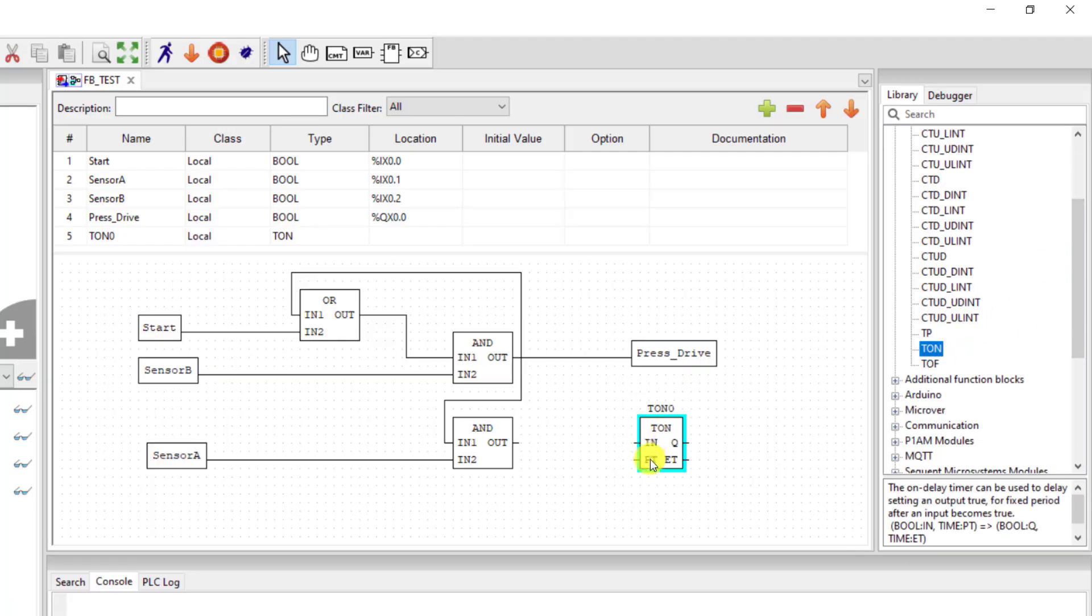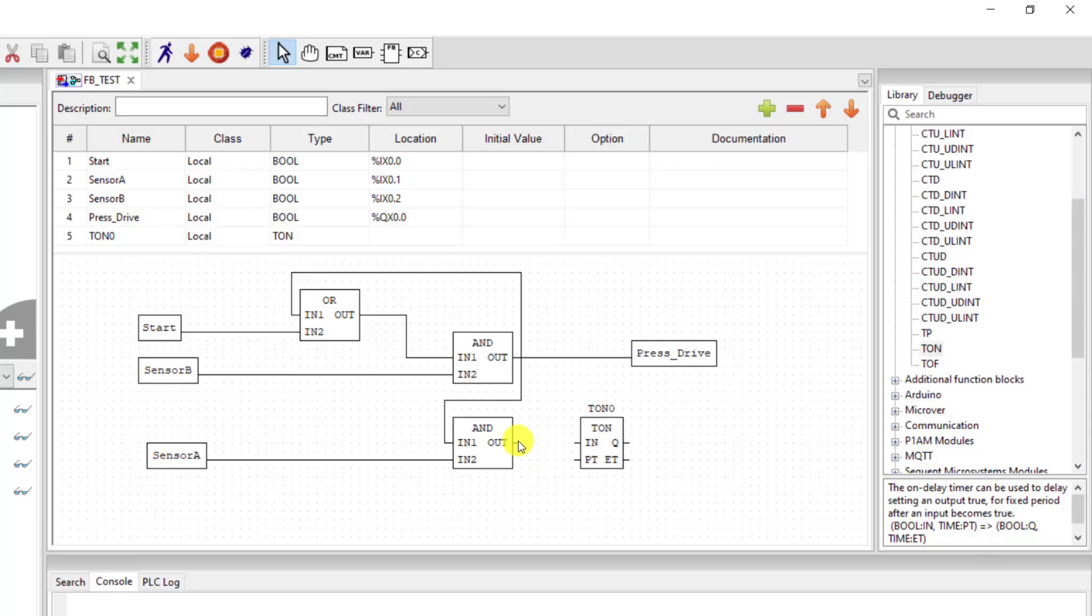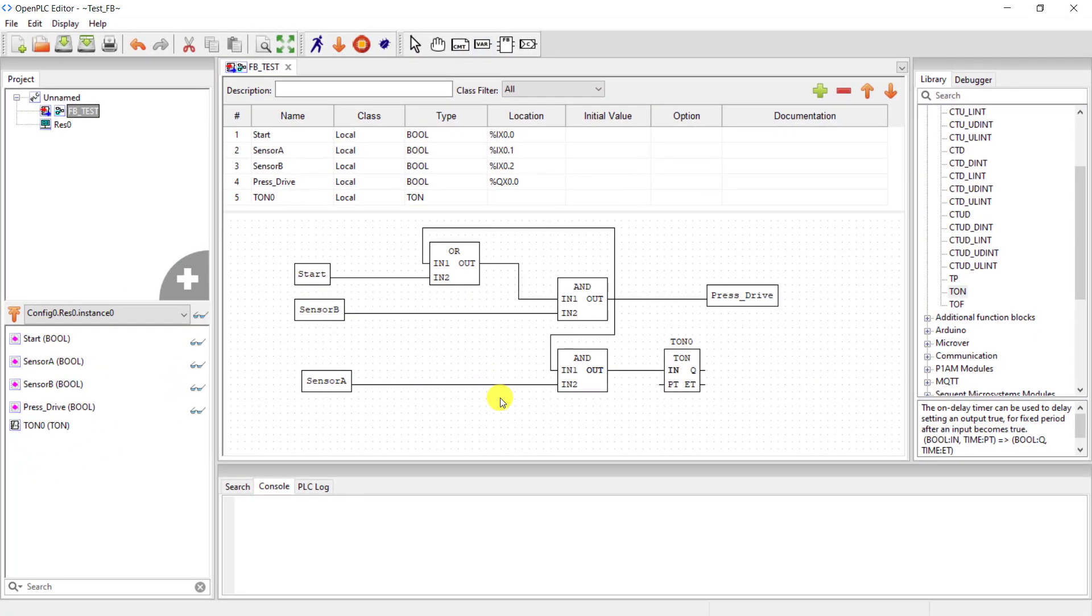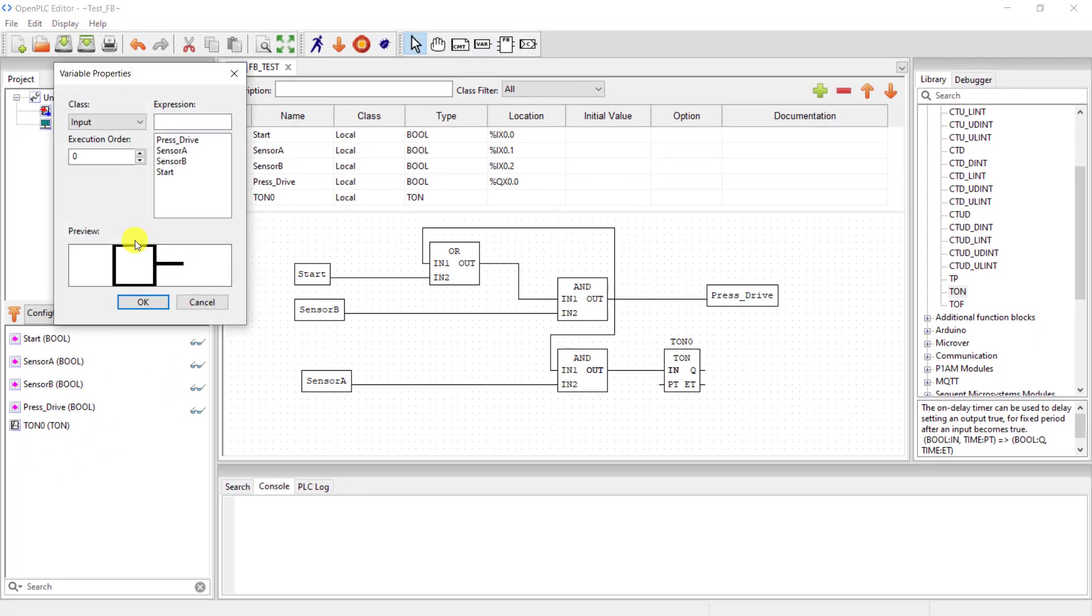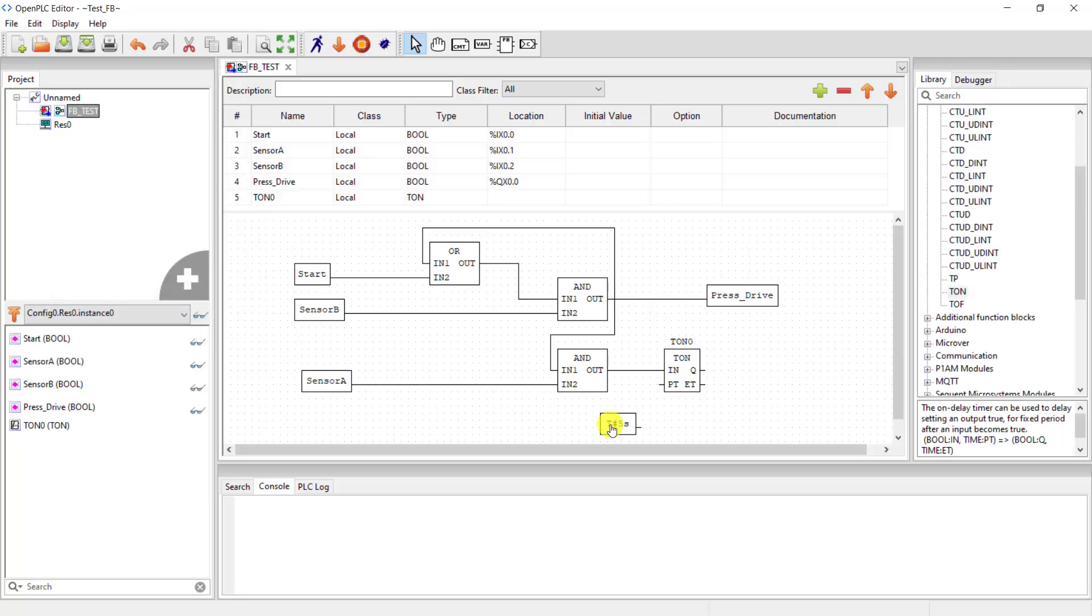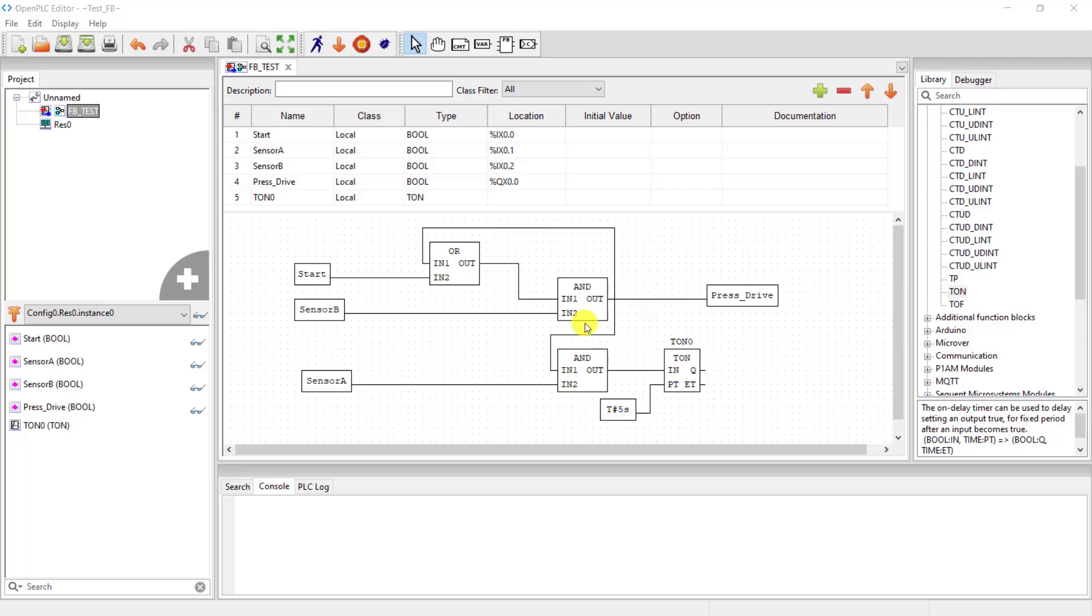Okay, I add the timer to it. I connect the output of the AND gate to the input of the timer which is an on-delay timer, and then I need to give it a preset time value. So I say T hash 5 seconds, indicating 5 seconds timing of this timer so that the pressure will be put on the material for 5 seconds.